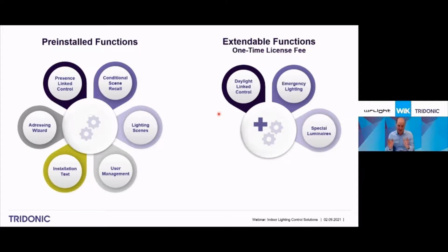We also have an app to create special luminaires. In special luminaires, you can group drivers or physical luminaires virtually together. For example, when you have a luminaire with a direct part and an indirect part going to the ceiling, on a standard DALI system that's recognized as two DALI addresses - say address 16 goes direct into the room, and address 73 goes indirect to the ceiling. With special luminaires, you can make one virtual luminaire out of that and control and balance the direct/indirect part with only one slider - a very easy to use and adaptive feature that makes such luminaires much more comfortable for end users.